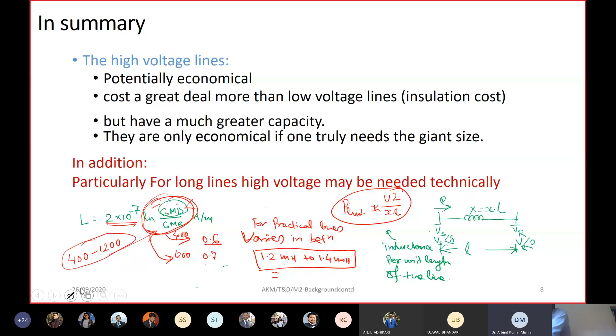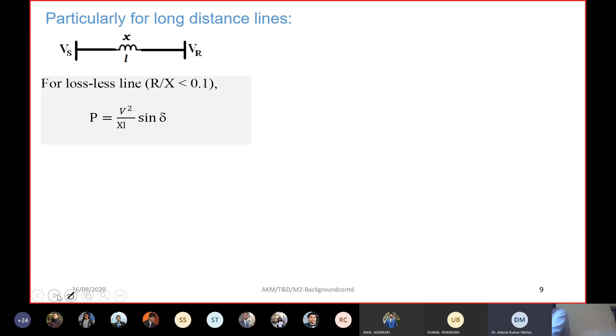So with this, what I want to convey is what I've just discussed. For practical lines, the value of per unit length reactance varies in a narrow range, and this has an already known limit. So what does it mean? That we can say P limit is proportional to V squared upon L, where L is the line length to be transported and V is the voltage.